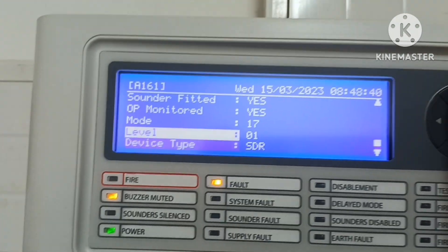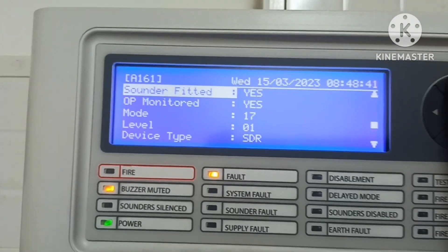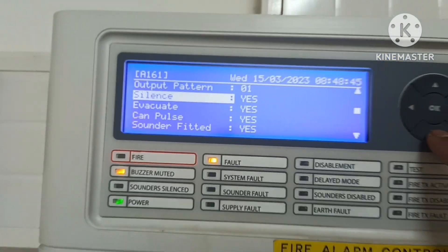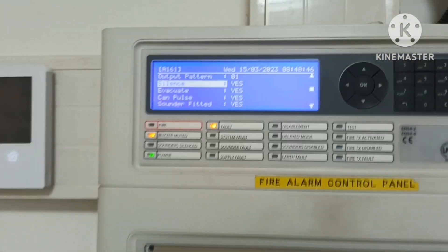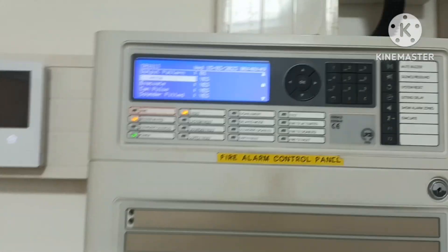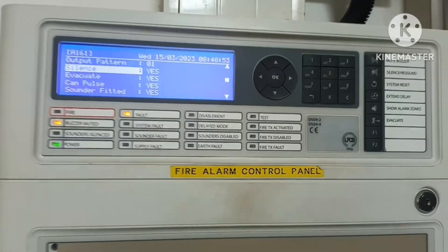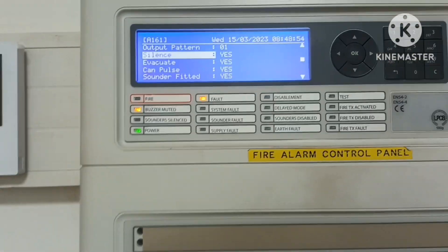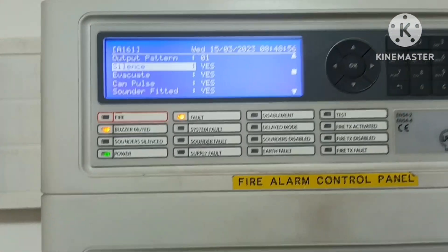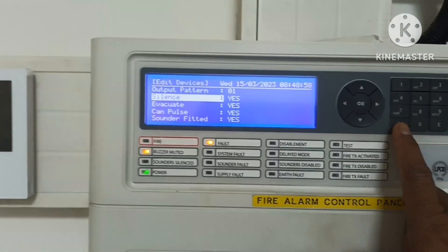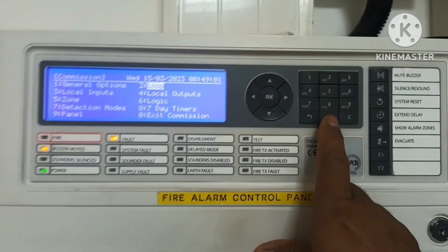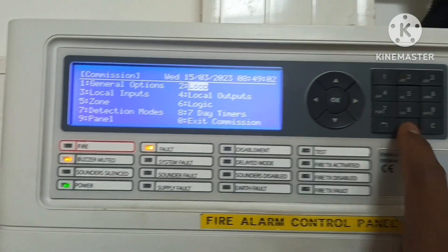For the output control module for sounders, the main things are device type and the Silence setting, so that you can silence your alarms in case of fire — meaning the hooters connected to the control relay module. Silence should be Yes.